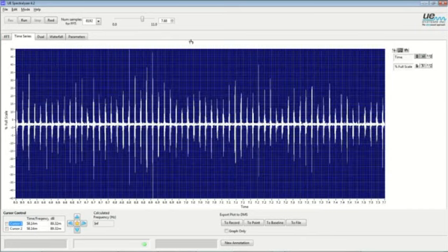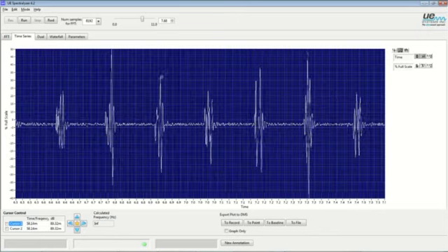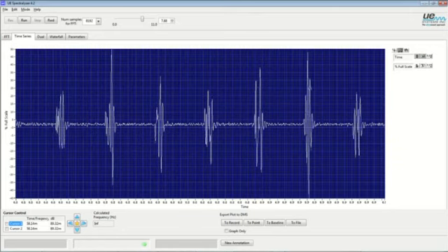We can see there are differences within the amplitude. That's part of the discharge intensity. And as we go in even further here, we can see there's changes in how long that's occurring. Not so much the spacing, because it's very early stages. But looking at the difference here between this next to the last one and the one previous, you can see how different it is in time relative to when the discharge is occurring.